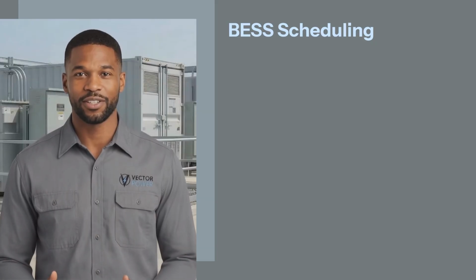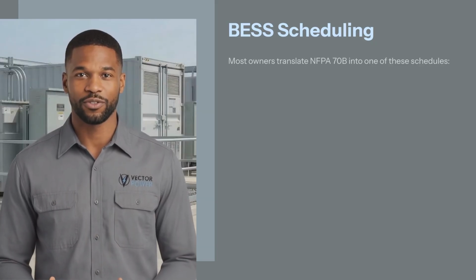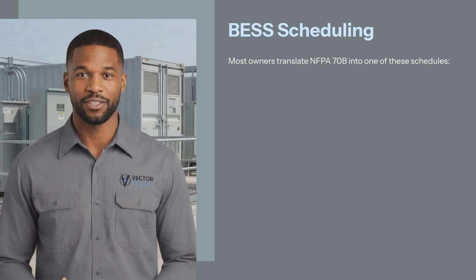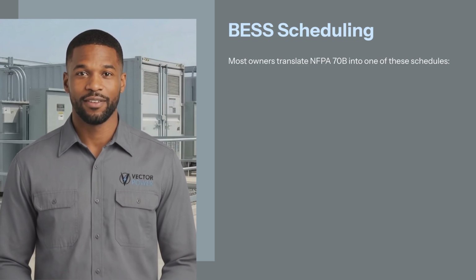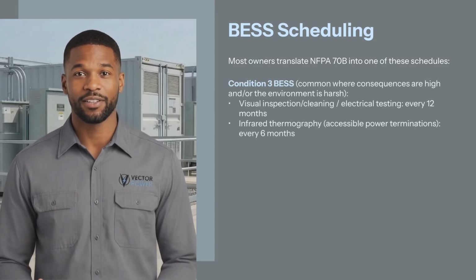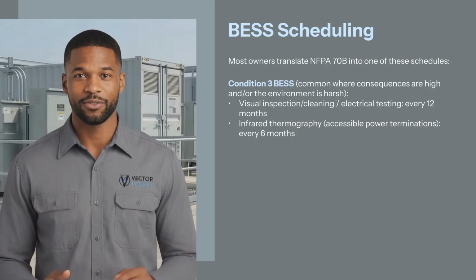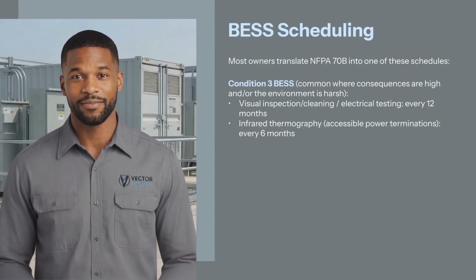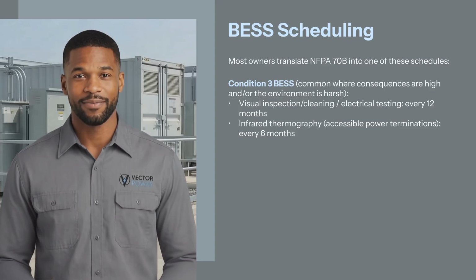Battery energy storage system scheduling. Most owners translate NFPA 70B into one of these schedules. Condition 3. Battery energy storage system common, where consequences are high and/or the environment is harsh. Visual inspection, cleaning, and electrical testing every 12 months. Infrared thermography, accessible power terminations, every 6 months. Condition 2.